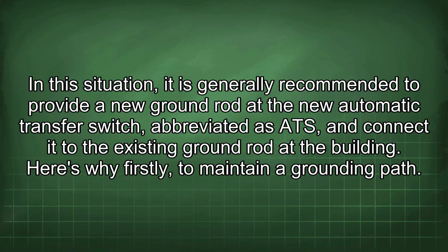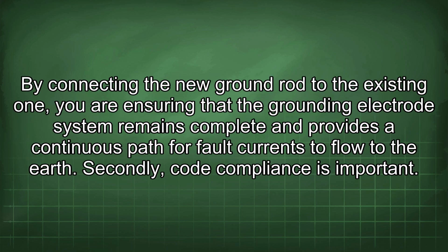In this situation, it is generally recommended to provide a new ground rod at the new automatic transfer switch, abbreviated as ATS, and connect it to the existing ground rod at the building. Here's why. Firstly, to maintain a grounding path. By connecting the new ground rod to the existing one, you are ensuring that the grounding electrode system remains complete and provides a continuous path for fault currents to flow to the earth.